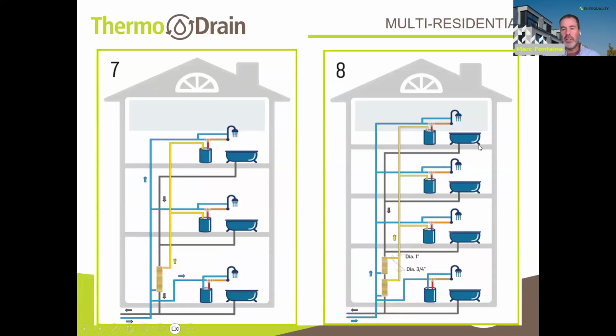In a building that's a little higher, so a 4-story building in this instance, we're usually limited in terms of flow rate through a ThermoDrain unit because the outlet is 3/4 inch. And so we usually go with this schematic where we put 2 units on top of one another and combine the outlets, so 2 times 3/4 inch together becomes a 1-inch equivalent line size, and that supplies the 3 water heaters. Alternatively, this unit right here could have been moved up a story and supplied 2 units, and then this one supplied 1. So there are some variations, depending on layout and how the builder wants to do things. But we found that this arrangement, where everything's at the same place at the bottom of the dwelling unit, is most popular.